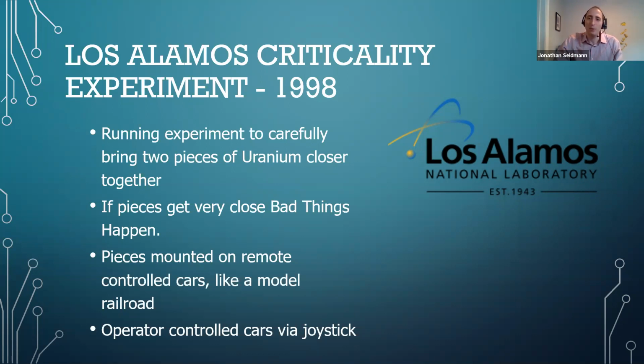So what happened to cause this? Turns out, as you may not be surprised, the joystick had failed. The processor reading the data from the joystick, reading which position it was in, recognized that the joystick itself had failed and sent an error message to the main controller reading the joystick data. When the joystick failed, it sent an error condition, which in this case was just an ASCII question mark, for those of you familiar with software.